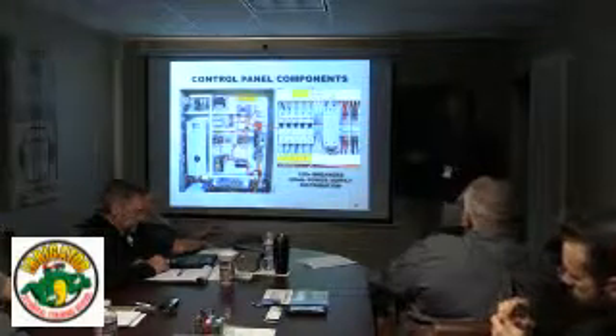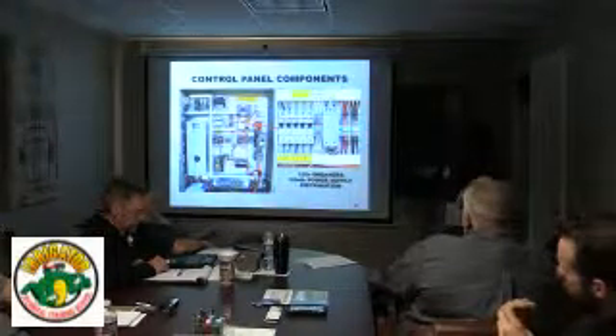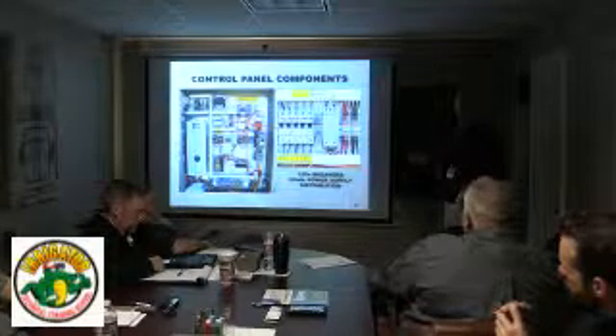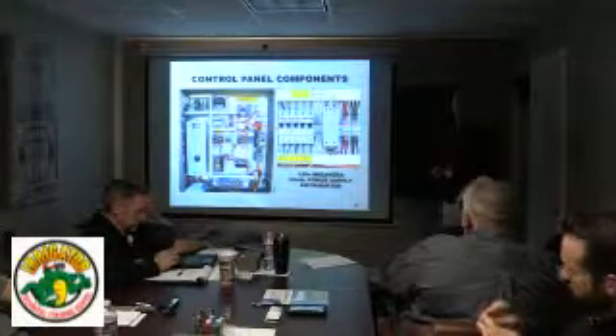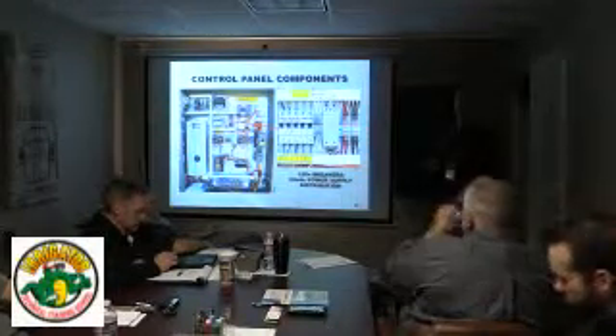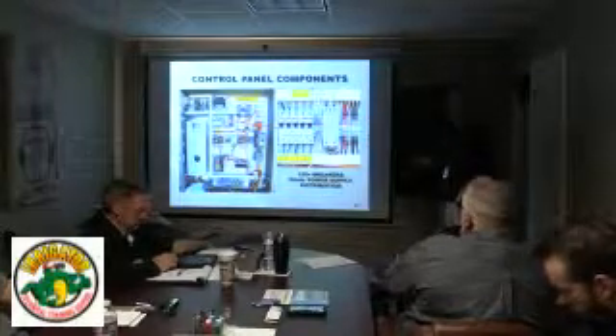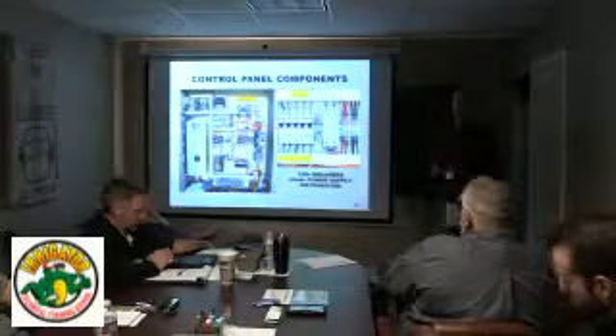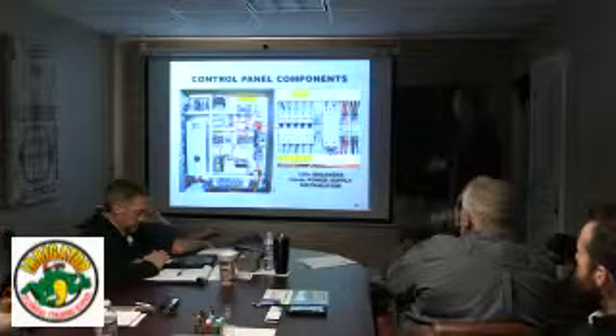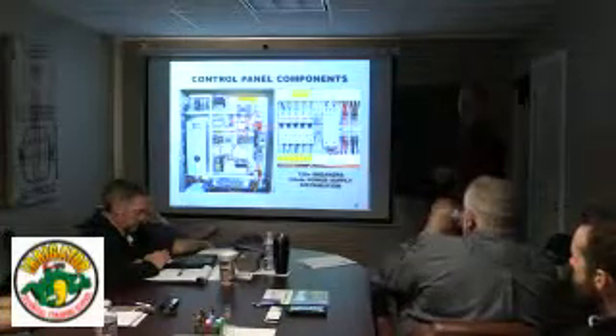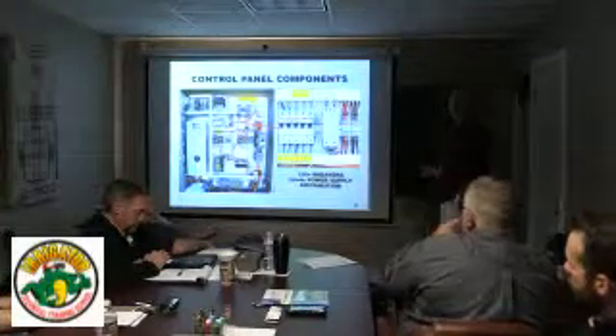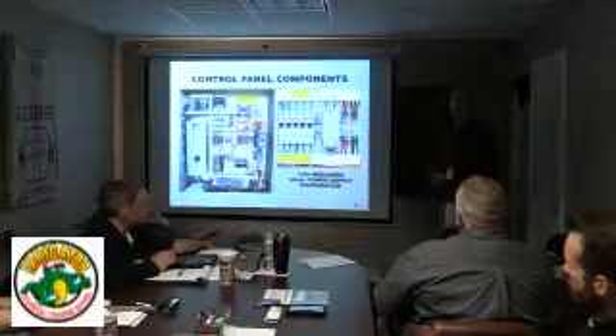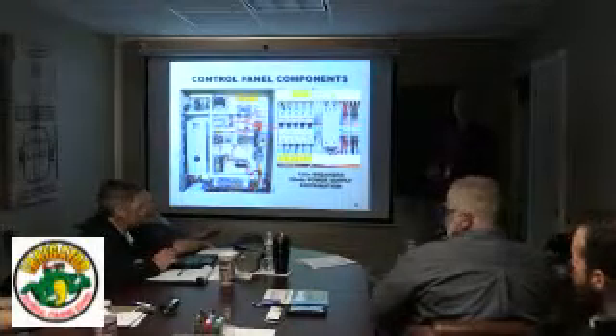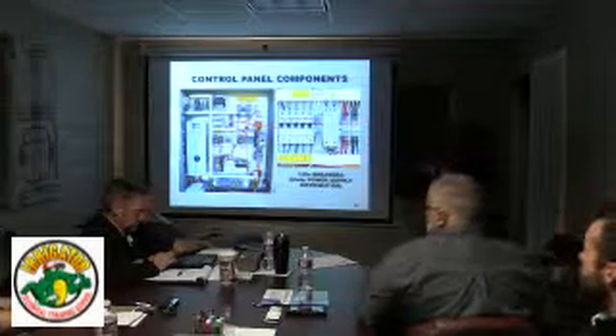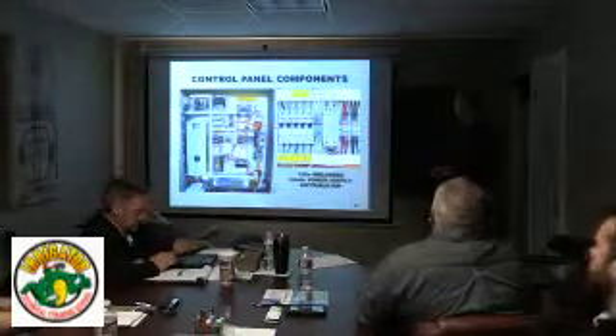You could have anything else out in this 24 volt DC supply chain, you know, the transducer or something shorting out, and it would cause everything to go out because it shorts out this power supply. So if you ever come across this, just pull that red wire out, measure it again, and make sure it's the power supply. We don't replace very many power supplies at all. Like I say, they're short circuit protected, and they just don't go bad very often at all.